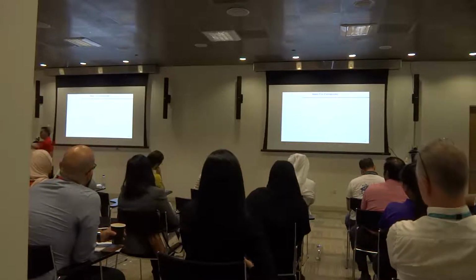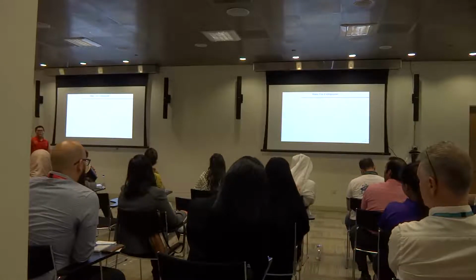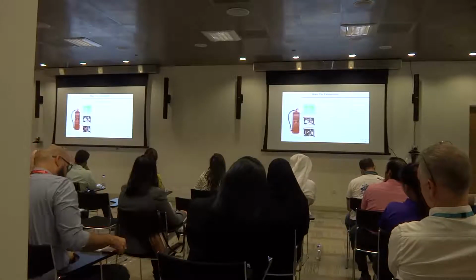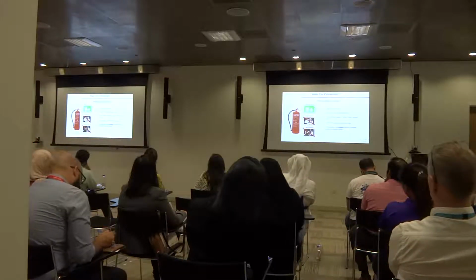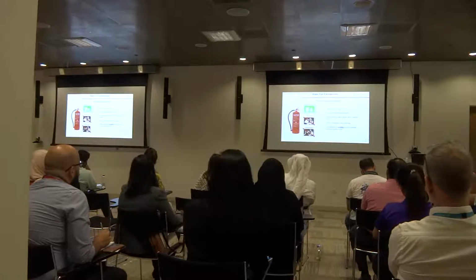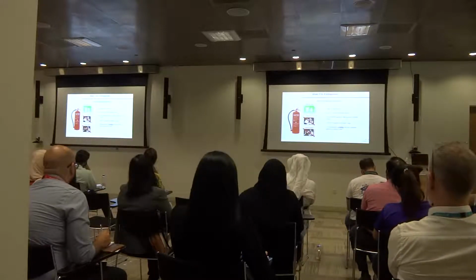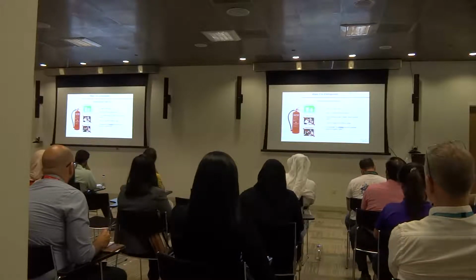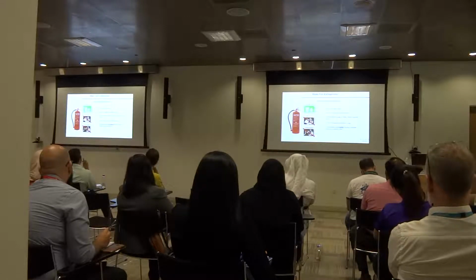Water extinguisher. Water extinguisher is safe to use for paper and ordinary combustible material. Pressurized water can be used for Class A fire. Up to 1 minute discharge time, has a pressure gauge to allow visual capacity check, 30 to 40 feet maximum effective range, and extinguishes by cooling burning material below the ignition point.